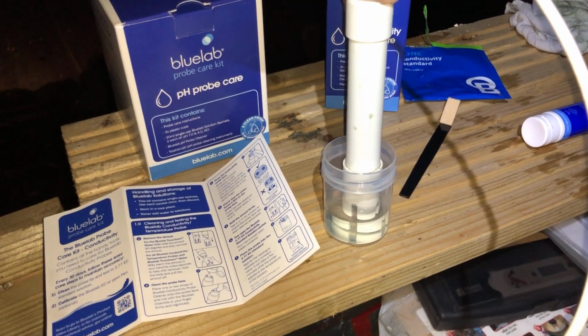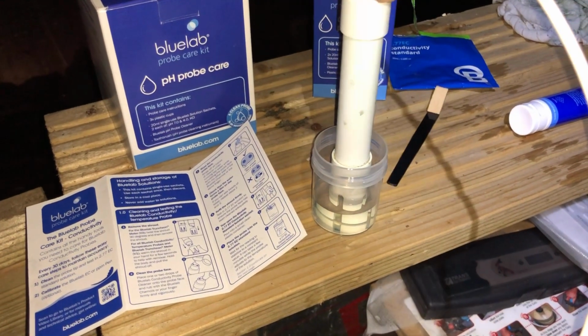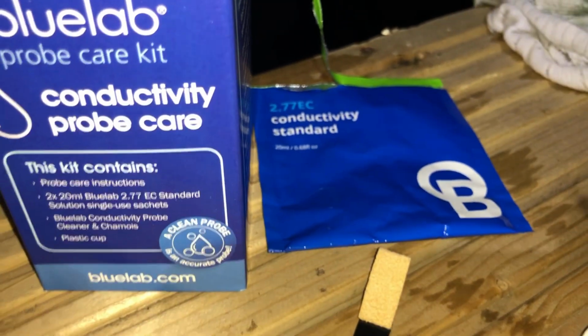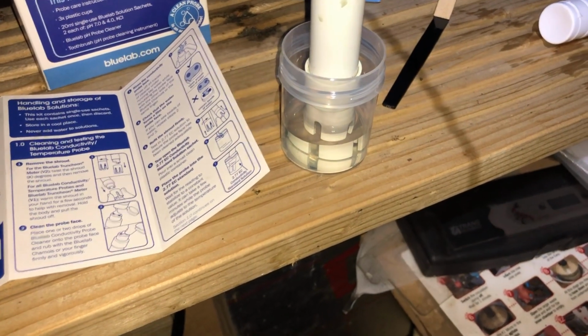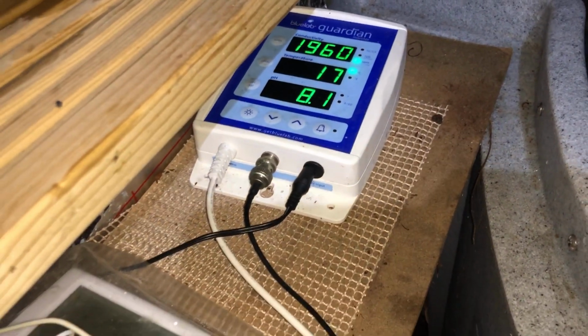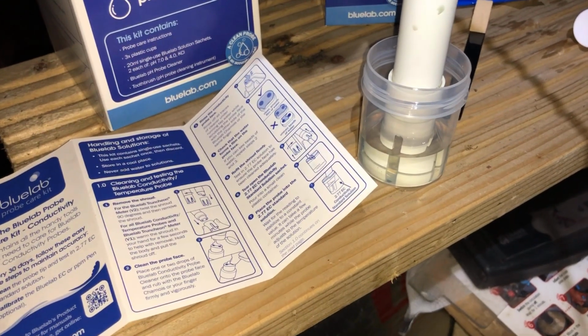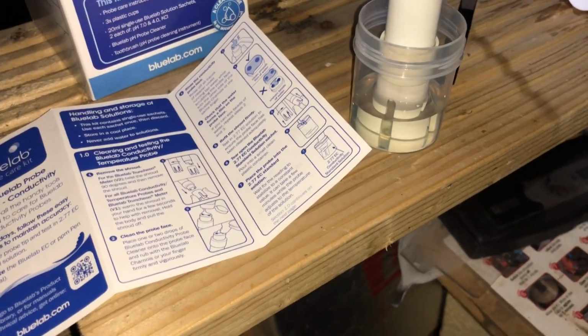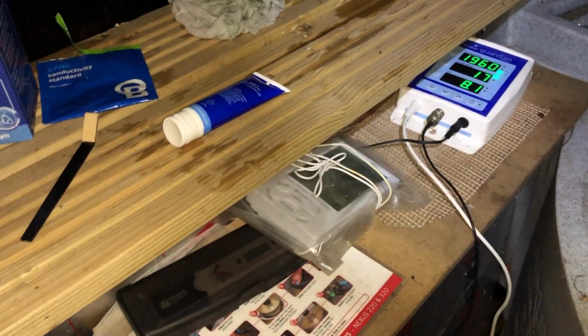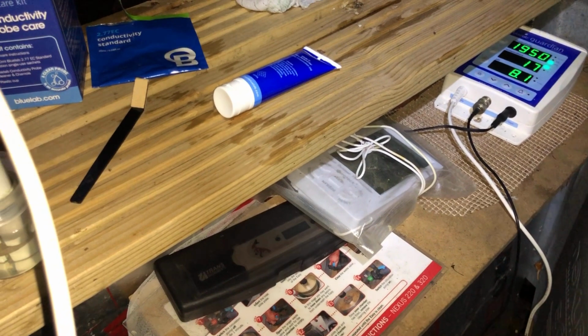Yeah, I'll crack on with the job. So I've cleaned the probe, got all the cleaner off of it, then you add it into the 2.77 EC conductivity standard. And then with that, your reading has to be 1940 ppm once stabilized. Okay, so then once that's done, you can calibrate your unit by pressing the calibration button on there for 3 seconds. I think I'm doing it all wrong just because I'm doing it one-handed. I should have both hands.